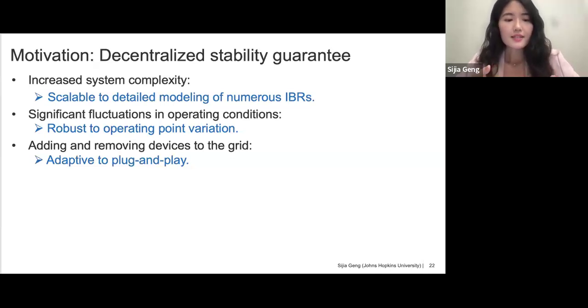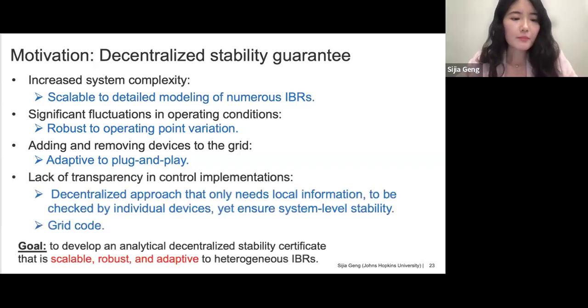Furthermore, there may be the case when adaptive plug and play happens in real time in future grids. The most suitable stability criteria should be able to adapt to such plug and play conditions. And last but not least, a barrier in the IBR world is the lack of transparency in control implementation. This creates the famous chicken and egg problem. On one hand, the IBR manufacturers do not have or care about the grid model and cannot ensure their device won't deteriorate the grid stability. On the other hand, the grid operator does not have access to accurate IBR models due to proprietary information. This altogether motivates us to pursue a decentralized approach that only needs local information to be checked by individual devices, but to ensure system-level stability.